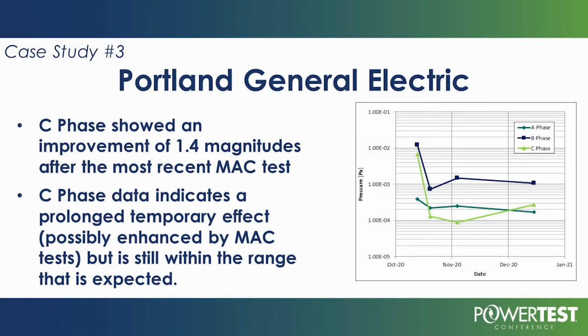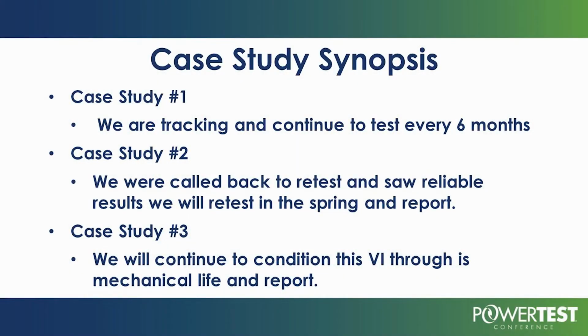C phase showed a greater effect. Like I said, depending upon the materials and the gases inside, we're going to see some interrupters that will show a greater than 1 order of magnitude improvement. Basically, the synopsis was we're tracking and we'll continue to test the power vac breakers every 6 months, and we'll report back on that as time goes on. Study 2, we were called back to retest these after 6 months, and we will every 6 months, and we've seen a reliable result in the spring report, and we'll be back again sometime this summer.